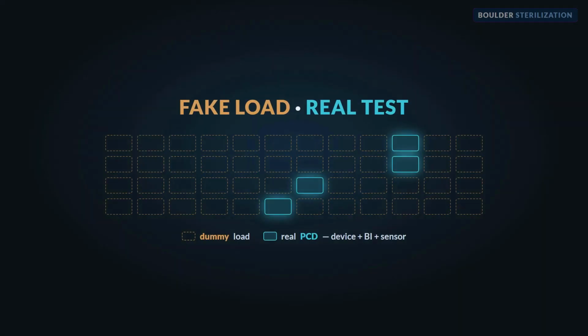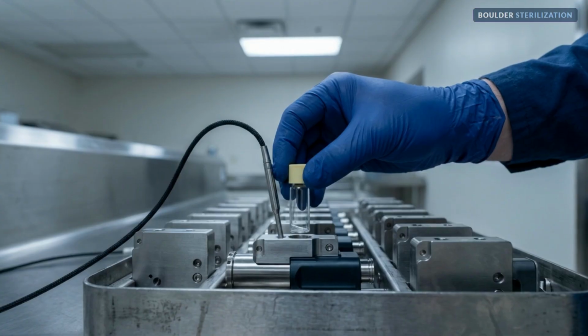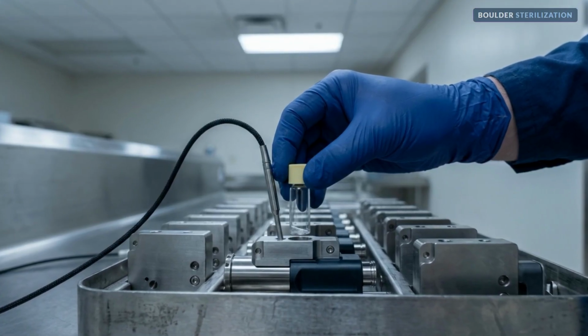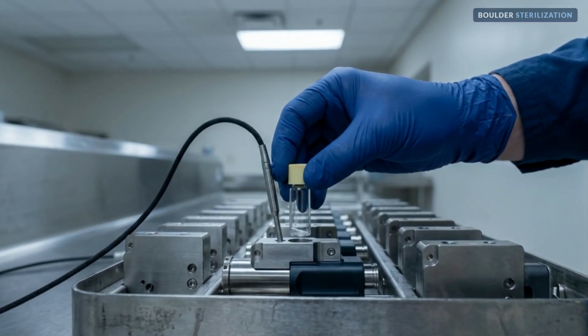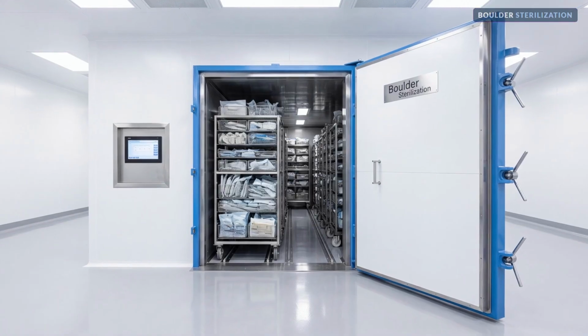Here is the elegant part. The load is fake, but the test inside it is real. The biological indicators and the sensors that actually prove sterility go inside real, fully functional devices, your actual product. We call them process challenge devices, and we scatter them through the dummy load. So the crowd filling your chamber is a fake. The test subjects hidden inside it are real. That is how you prove the sterilant reached the hardest spot in a packed load and killed everything there.